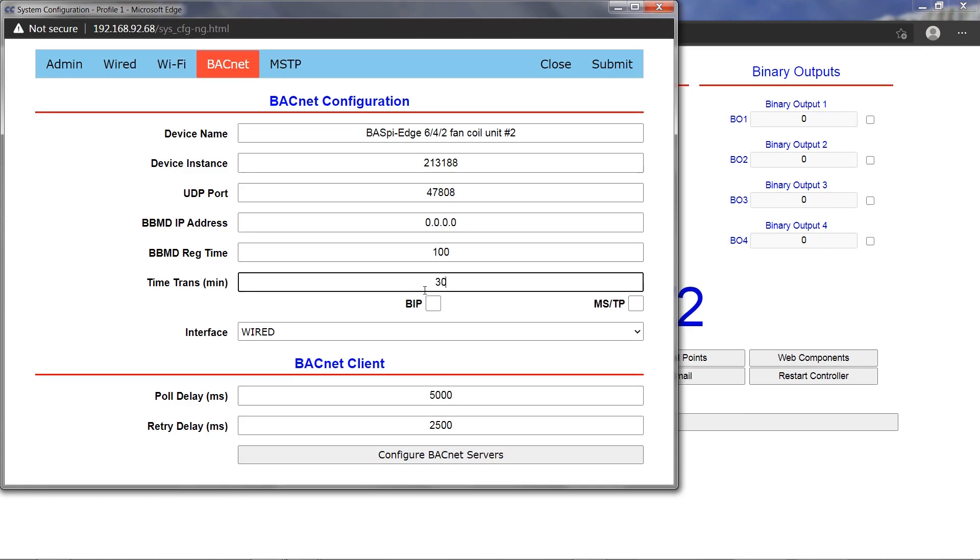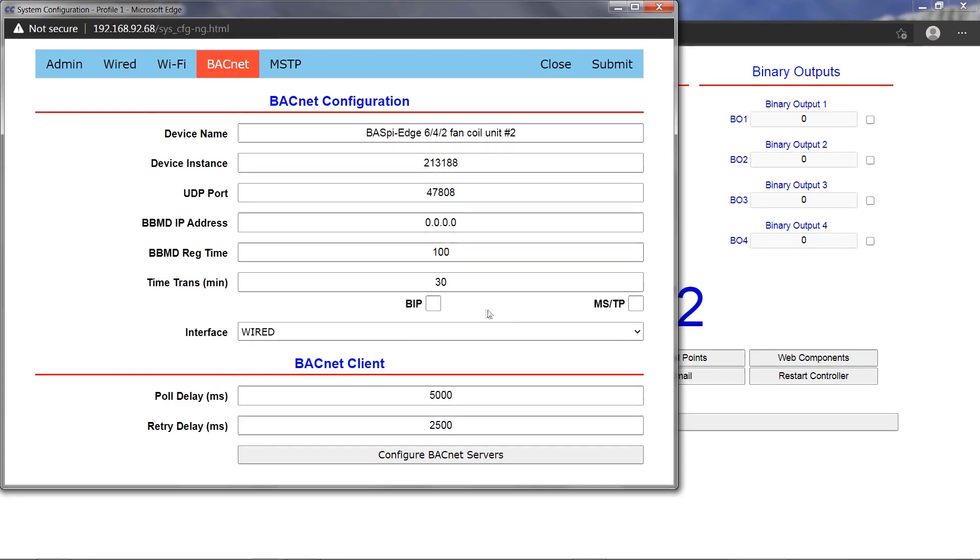Below the interval setting are the checkmarks for time transmission over BACnet IP, the BIP checkmark, or BACnet MSTP, the MSTP checkmark. The accuracy of the transmitted time relies on the NTP server obtained time configured from the set time webpage.